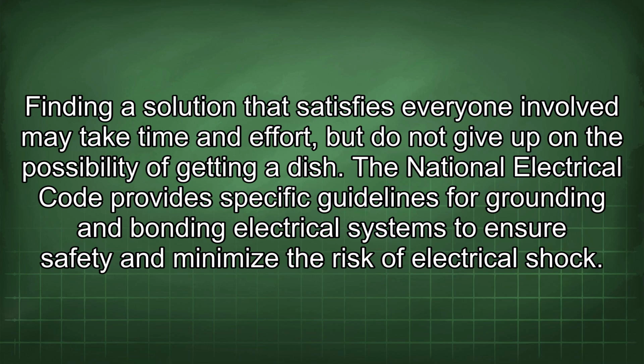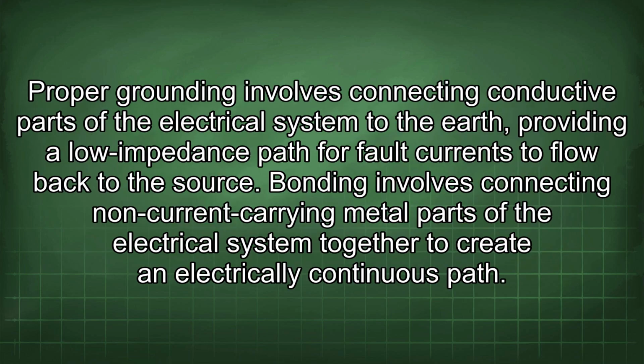The National Electrical Code provides specific guidelines for grounding and bonding electrical systems to ensure safety and minimize the risk of electrical shock. Proper grounding involves connecting conductive parts of the electrical system to the earth, providing a low impedance path for fault currents to flow back to the source. Bonding involves connecting non-current carrying metal parts of the electrical system together to create an electrically continuous path.